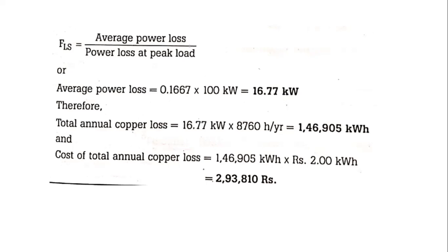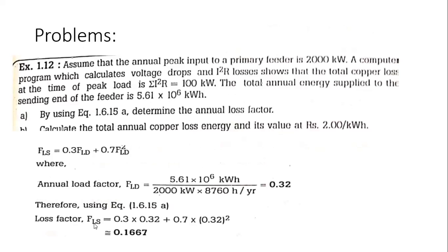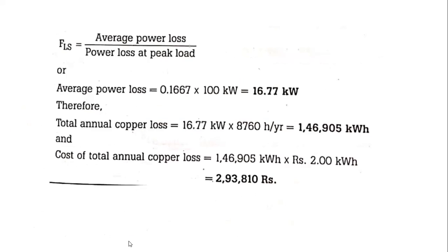What is meant by FLS? That is the loss factor. What is that formula? Average power losses by power losses at peak load. We already calculated the loss factor value, that is 0.167. FLS is equal to 0.167.